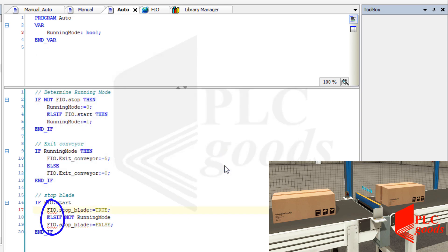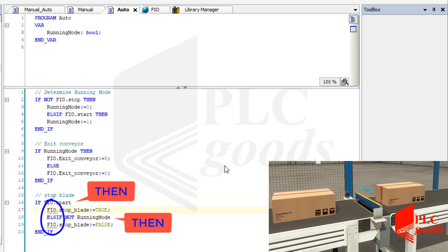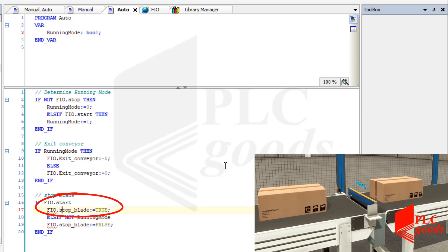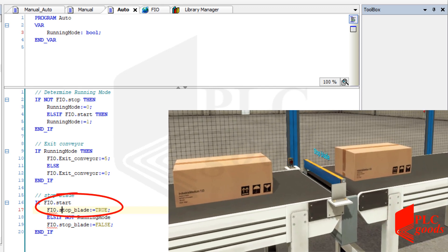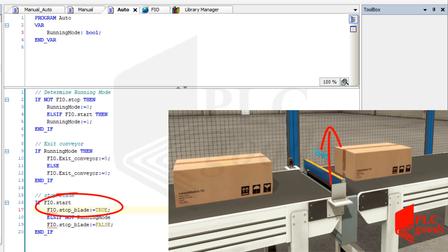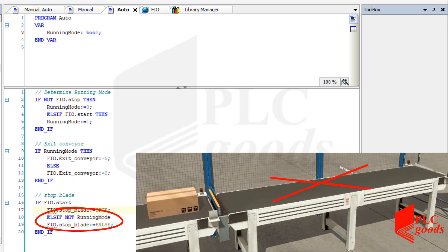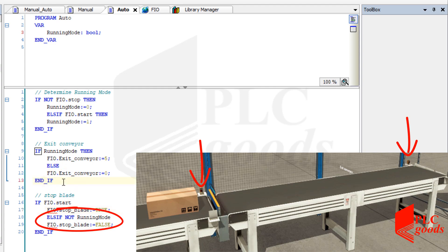As you see there are two red lines because after each condition I've not written 'then'. Now let's continue. There is another condition to turn on the stop blade: after passing each box, when this sensor produces a positive signal edge, the stop blade must be enabled. Also, when there are not any boxes on the exit conveyor the stop blade must be off. Therefore I'll need to use these two sensors to count the current boxes on the second conveyor.